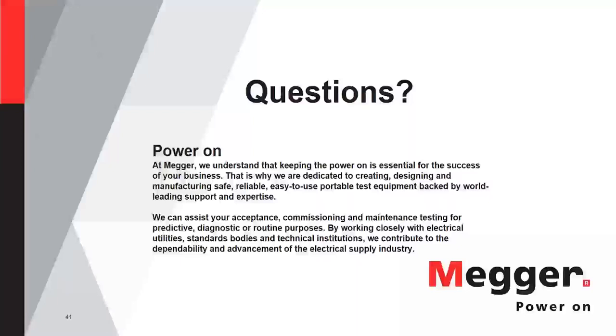Okay, thank you, Robert. On to the next question. For VRLA, if you continue to take ohmic values every 6 months, you are not required to ever do a discharge test, correct? This question is similar to the one I answered before. As I said, it's not very specific. If you read the table as it is, the interpretation is that you definitely need to still do ohmic testing every 6 months, and just every 3 years you decide whether you want to do ohmic testing or a capacity test. But every 6 months, the way we see it, you still need to do it.